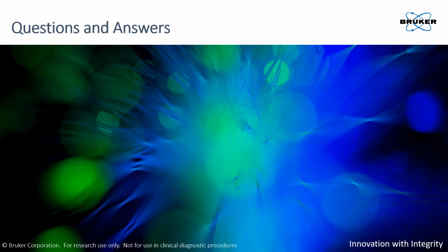Speaking of the methods, yes, methods can be changed. Obviously, the instrument is supplied with pre-developed methods. And these pre-developed methods, one for LCMS and one for GC-APCI, are really needed to make use of the database also provided with the system. They kind of work in conjunction together as one standardized solution, and that kind of makes everything click. However, if you prefer to use instrument for some other applications that do not rely on this existing database, you're totally free to use any other custom methods at your convenience.